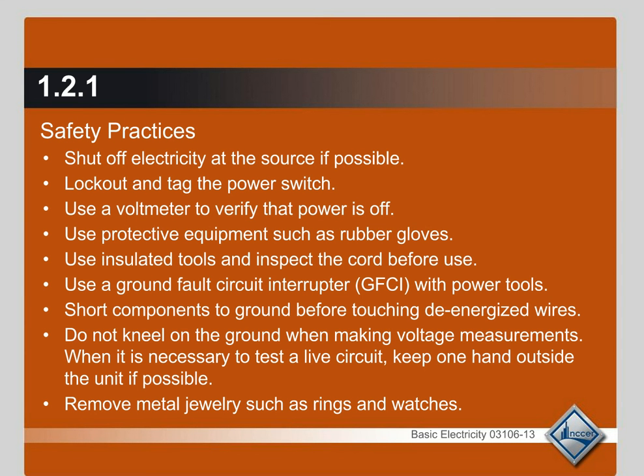Shut off the electricity at the source — go to the disconnect at the unit so you know for sure it's off, not just the circuit breaker inside the house. If you do disconnect at the circuit breaker panel, use a lockout tag following your company's lockout and tagging procedures. Remember the safety module example where the service disconnect was hotwired — you pull the disconnect thinking there's no power, when in fact it was hotwired because the service disconnect was faulty. Use your voltmeter every time, triple check that power is off, and wear leather or rubber gloves for protection.